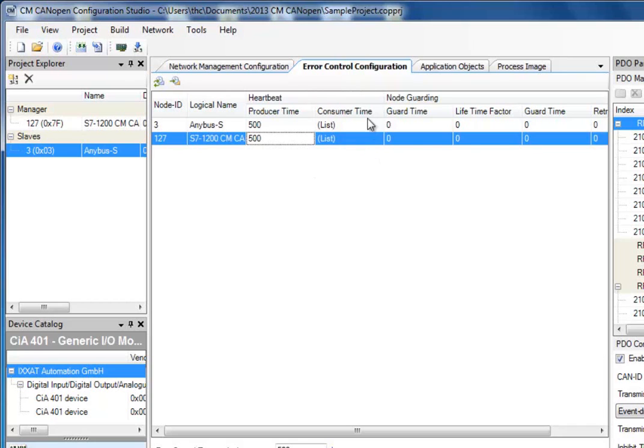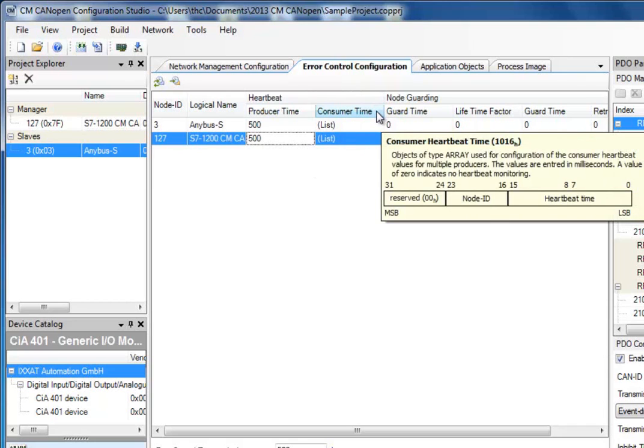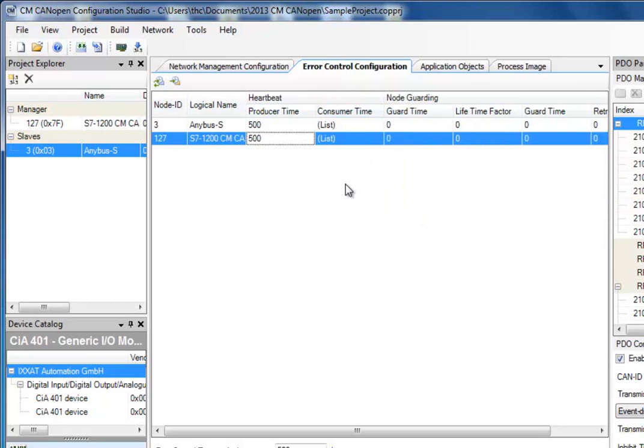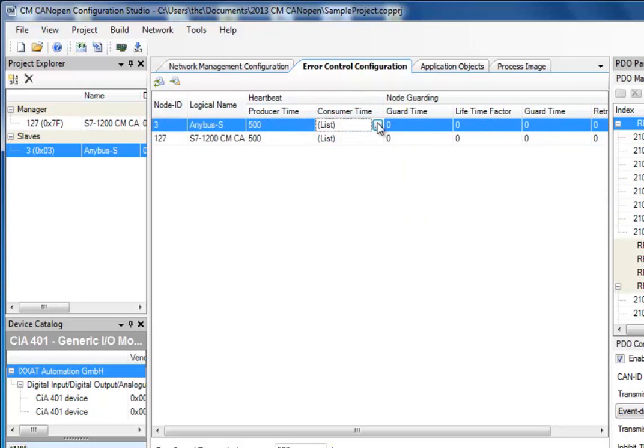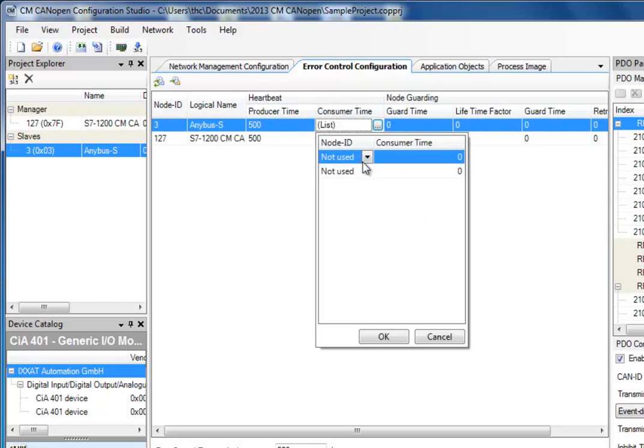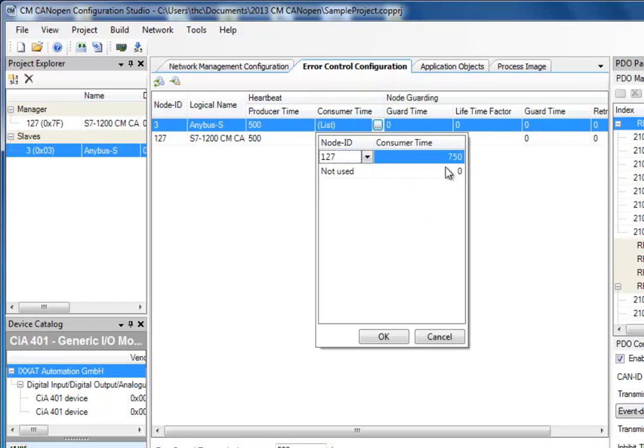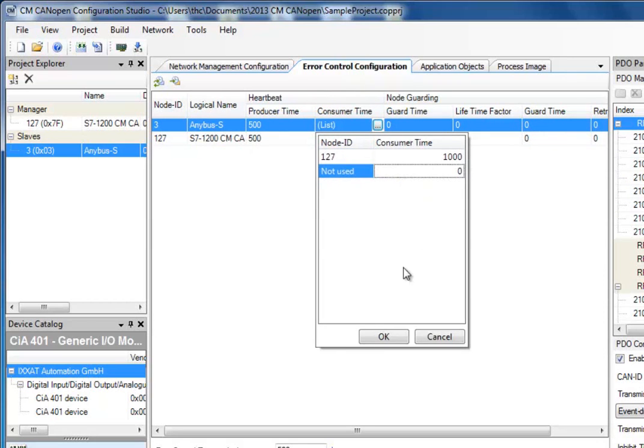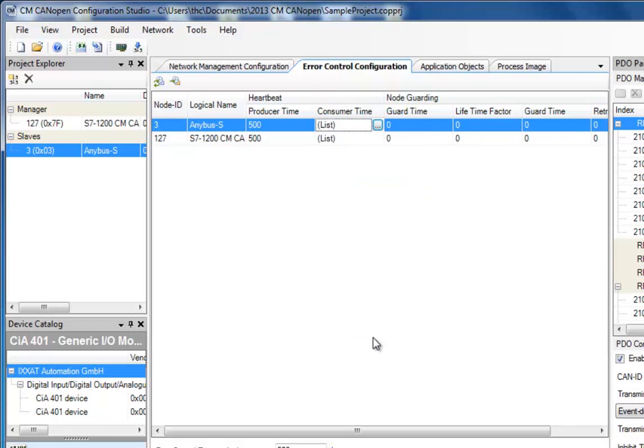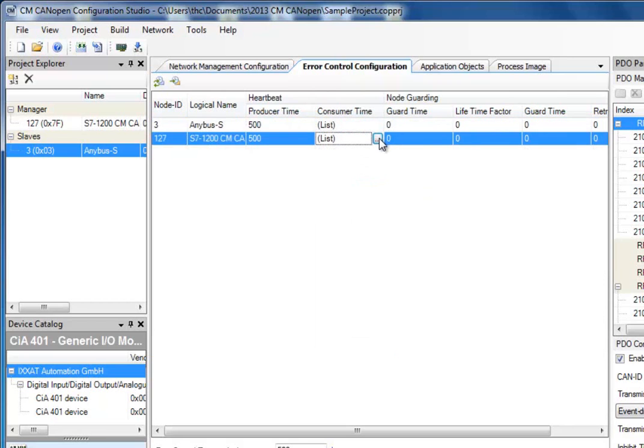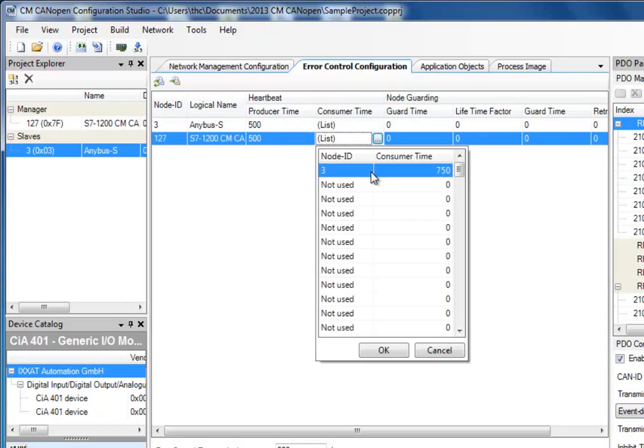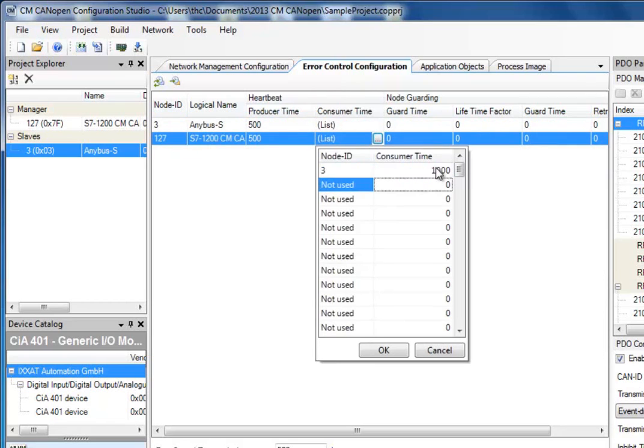I also need to select Consumer Time, which is the time frame in which the receiving node expects to receive the heartbeats. For my Anybus S, I specify that we should receive heartbeats from the S7-1200, located on node ID 127, once every second. If it does not, it will send an alert. We do the same thing for the S7-1200. If it does not receive a heartbeat from the Anybus S on node 3 every second, it will alert.